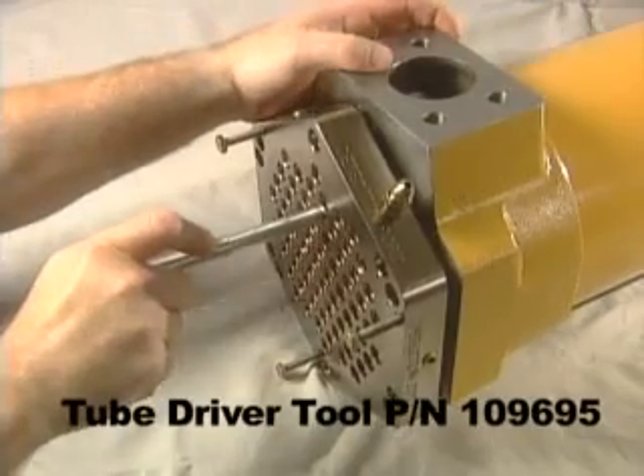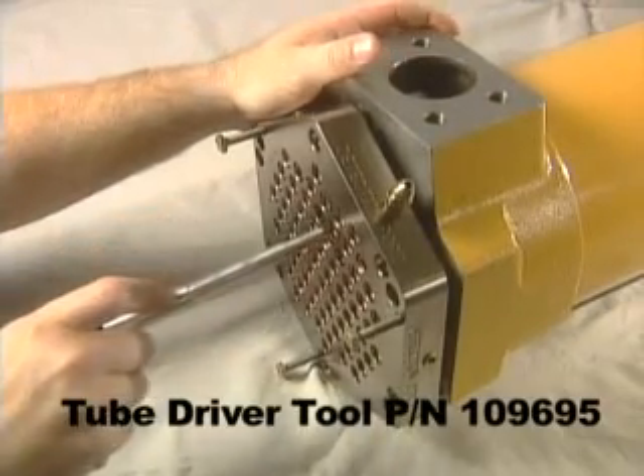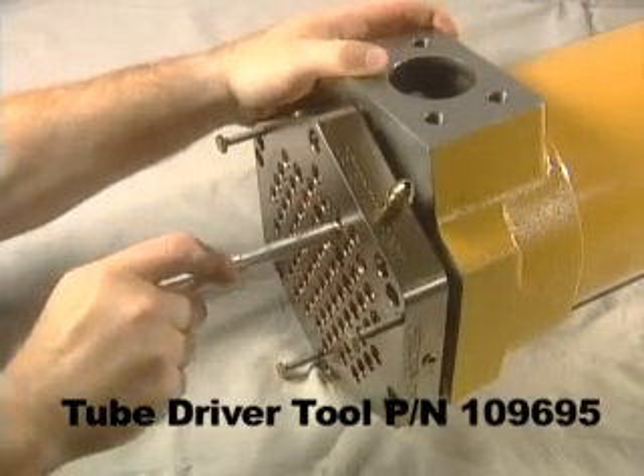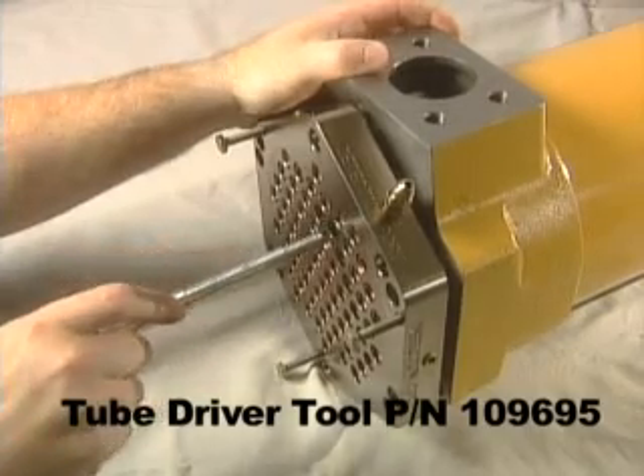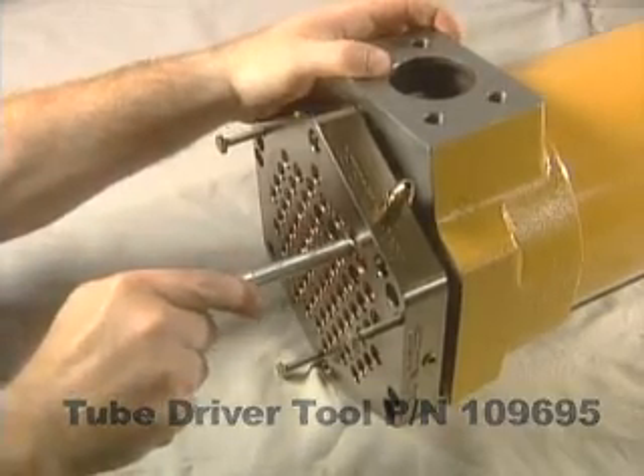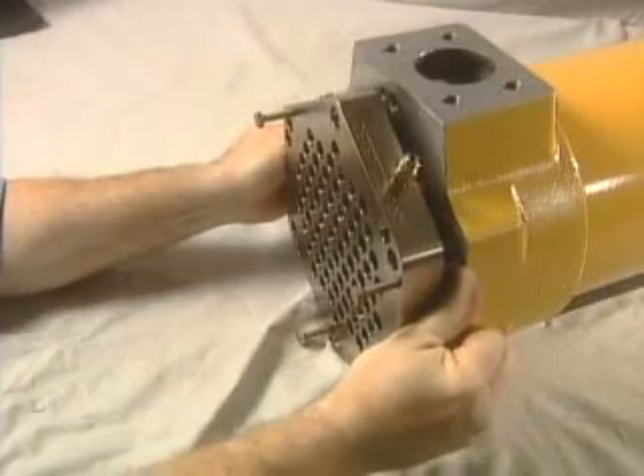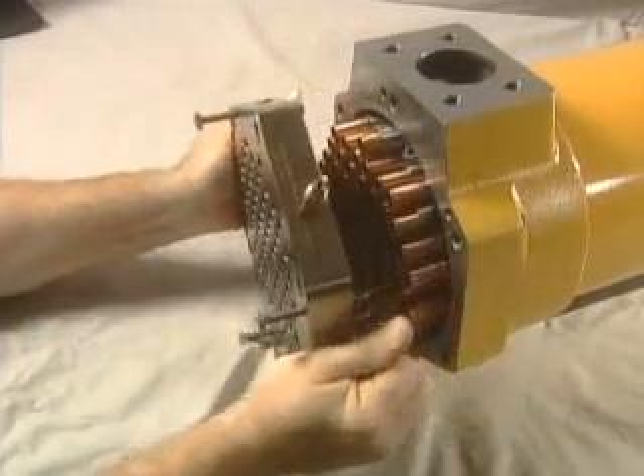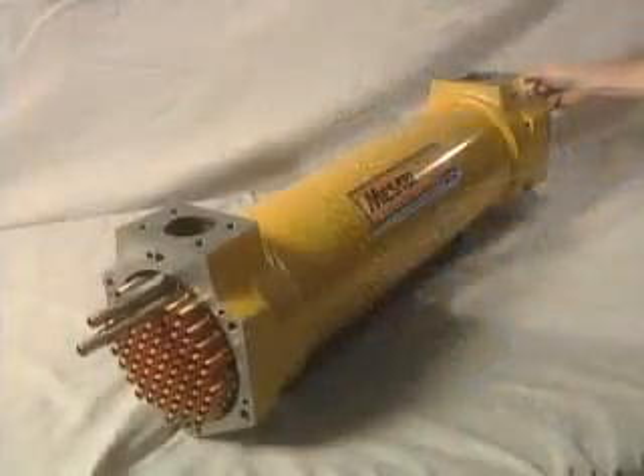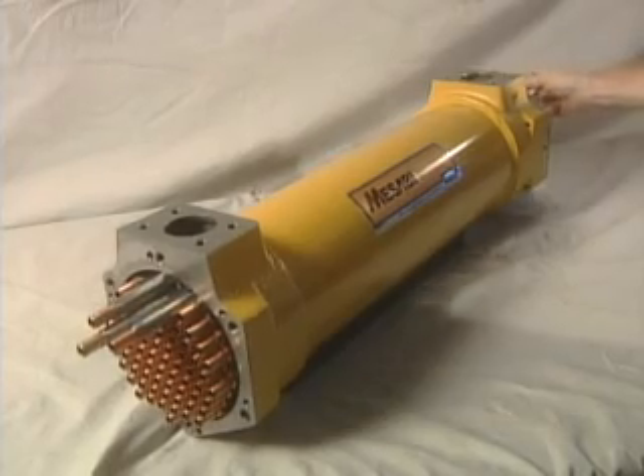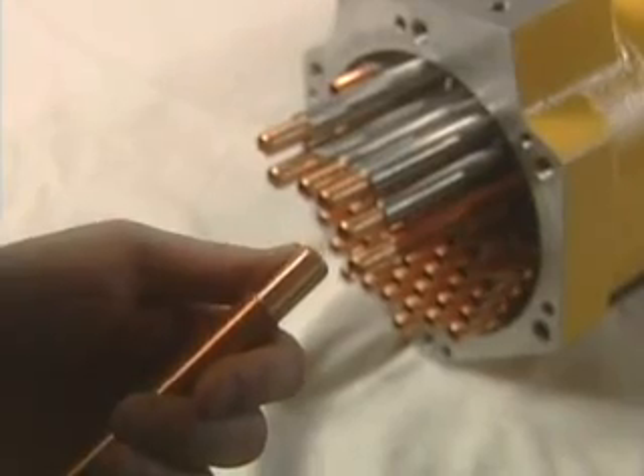Some tubes may stay attached to the header and will have to be pushed out of their seals and back into the baffle assembly. Use the tube driver tool to accomplish this. Remove the second header in the same manner as the first. Push the tubes from the baffle assembly using the tube driver tool. Check the tube ends for any damage.